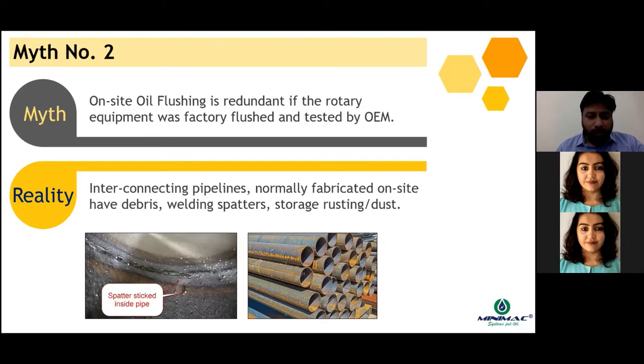As a matter of fact, we all know that whenever the equipment lubrication system is installed at the site, the lubricating points would be far away from the lubrication system. So the bearings or the other lubrication points would be maybe around a few meters away, and you would have to do some installations with your pipeline network at the site itself. So while you have received your equipment from the OEM, that's the lubrication system and the bearings which are pre-flushed at the factory by the OEM, the network pipeline or the piping which you construct or erect at the site might have a lot of welding spatters and debris inside.